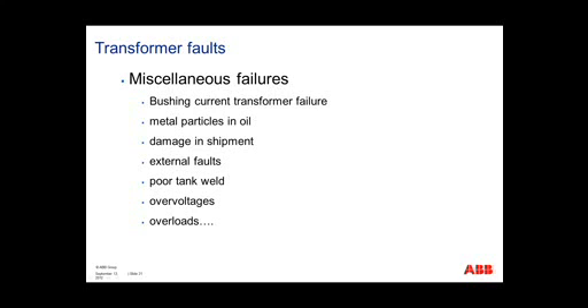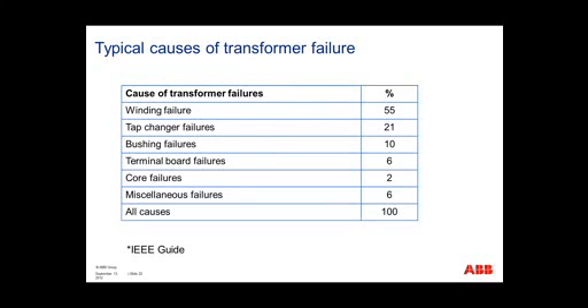Miscellaneous failures, bushings, current transformer failure, particles in the oil, damage in shipment, external faults, poor tank weld, overvoltages, and overloads. This is a page from the IEEE guide. It shows what percentage of the causes of transformer failures occurred in the U.S. At the top of the list, you'll have winding failures. It's 55%. 21% is tap changer failures, 10% bushing failures, and so on.